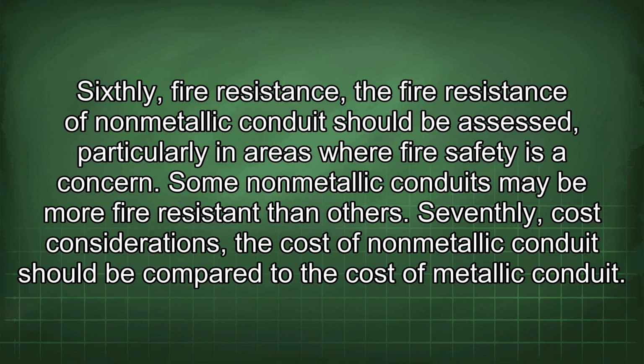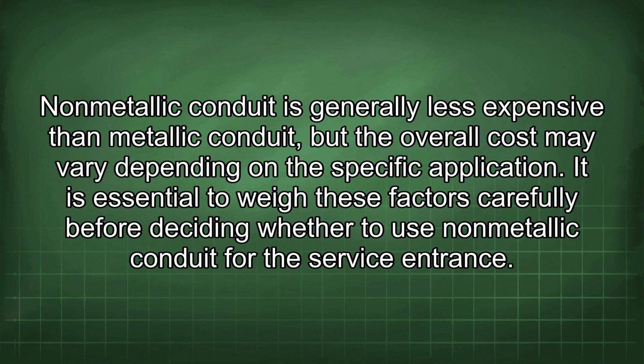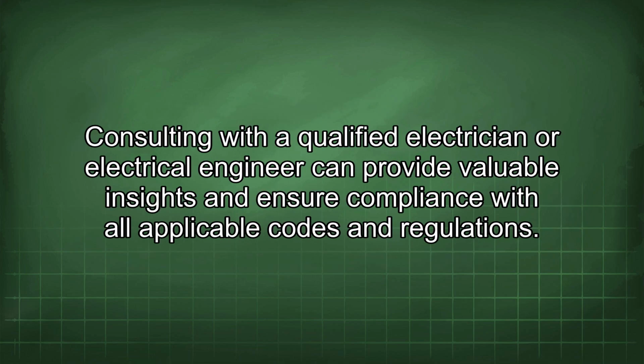Sixthly, fire resistance. The fire resistance of non-metallic conduit should be assessed, particularly in areas where fire safety is a concern. Some non-metallic conduits may be more fire resistant than others. Seventhly, cost considerations. The cost of non-metallic conduit should be compared to the cost of metallic conduit. Non-metallic conduit is generally less expensive than metallic conduit, but the overall cost may vary depending on the specific application. It is essential to weigh these factors carefully before deciding whether to use non-metallic conduit for the service entrance. Consulting with a qualified electrician or electrical engineer can provide valuable insights and ensure compliance with all applicable codes and regulations.